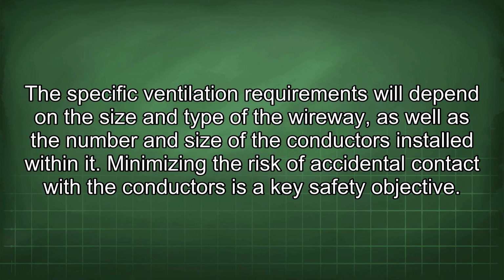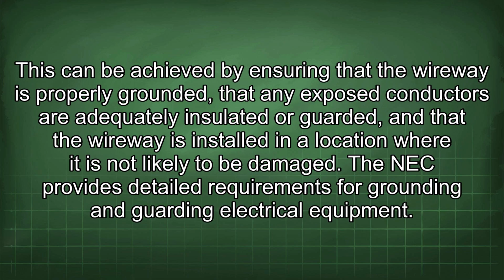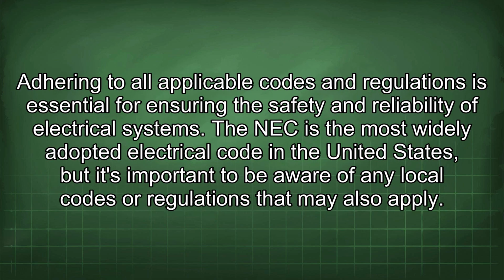Minimizing the risk of accidental contact with the conductors is a key safety objective. This can be achieved by ensuring that the wireway is properly grounded, that any exposed conductors are adequately insulated or guarded, and that the wireway is installed in a location where it is not likely to be damaged. The NEC provides detailed requirements for grounding and guarding electrical equipment. Adhering to all applicable codes and regulations is essential for ensuring the safety and reliability of electrical systems.